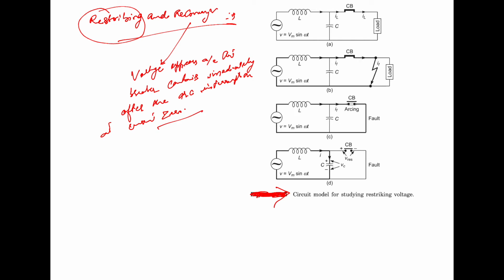Initially, this voltage is the result of the transient response of the system formed by the breaker contacts and the L and C parameters. Now this figure shows the model that we use for studying the restriking voltage. In this figure, the system inductance is shown lumped, that is L. And then we have the capacitance of the system, mostly the stray capacitance, which is also shown lumped here. Figure A shows the system in the pre-fault healthy condition with the current IL flowing through the closed contacts of the circuit breaker. The situation after the occurrence of the fault is shown in figure B, with the current IF flowing into the fault through the closed contacts of this circuit breaker.